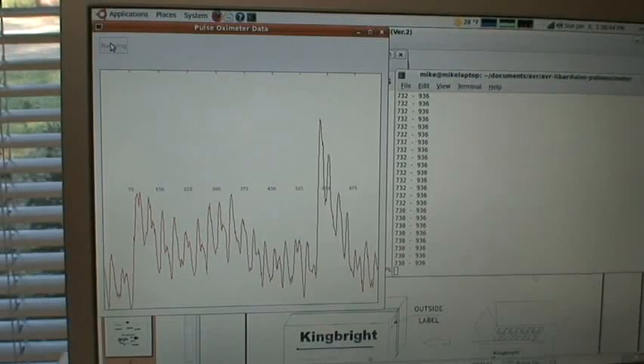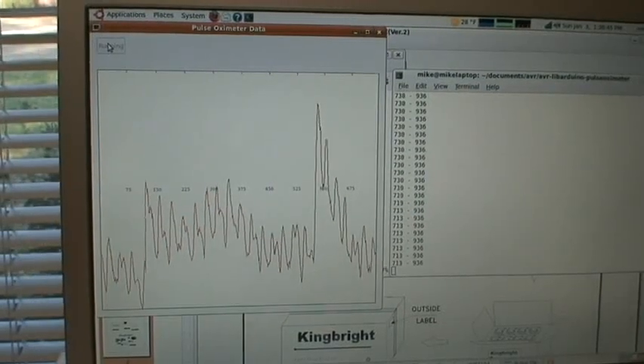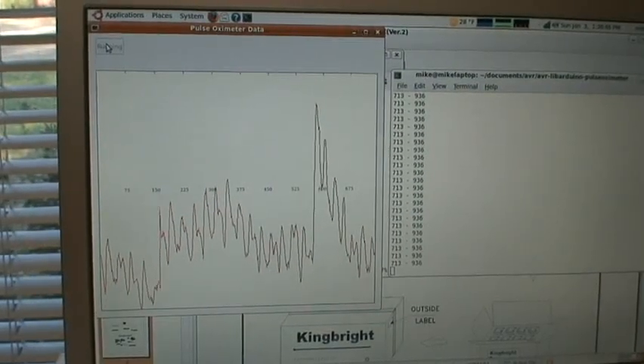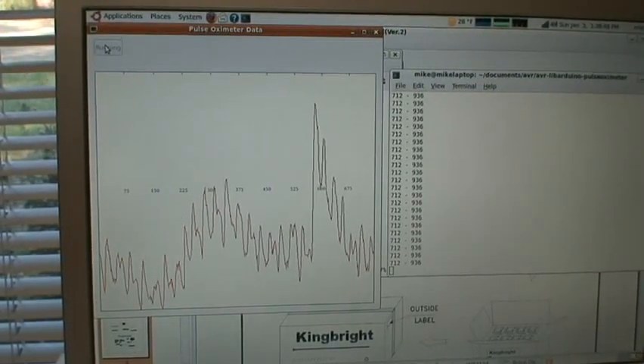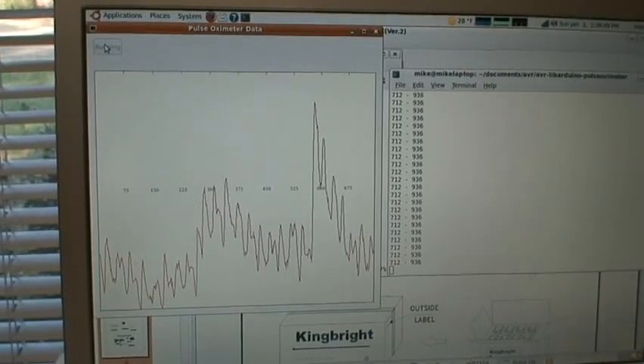So with the red LED we're shining a red light, it's going through our finger, and some amount of the red light is being absorbed by our pulse. We're measuring just the leftover light that has not been absorbed by our pulse.